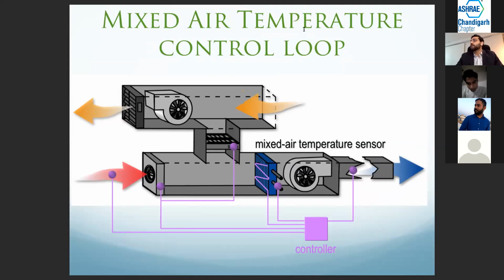Next is the mixed air temperature control loop. We just talked about this, but now we've added a sensor here. It is typically an averaging type sensor because it detects the temperature at various points through this tube, and then sends a signal to the controller, where the controller is able to make a better decision on what the temperature of the air is, instead of waiting for it to go all the way down in the space and then detecting it here.